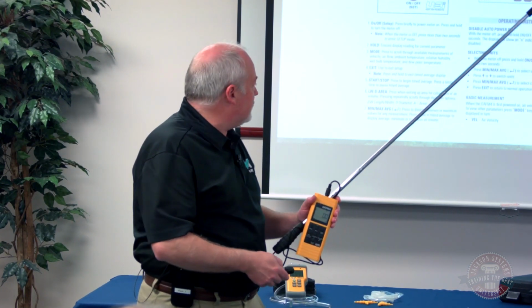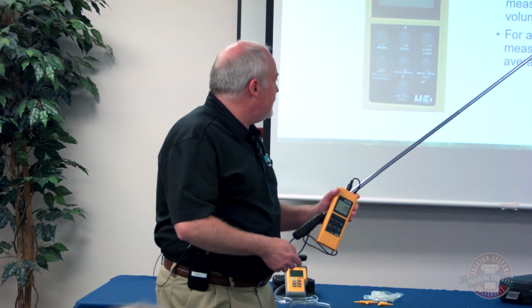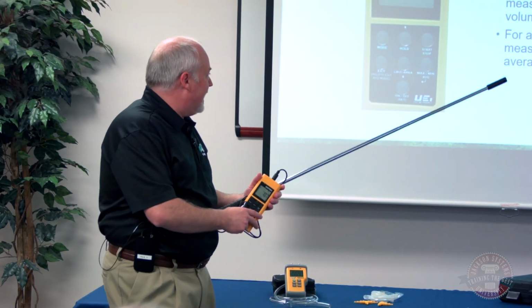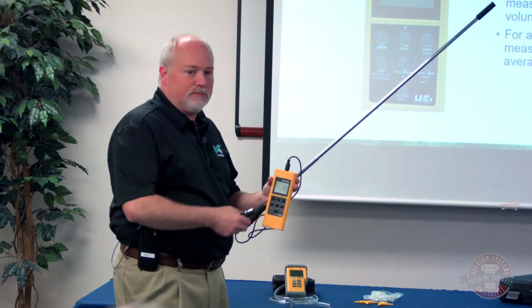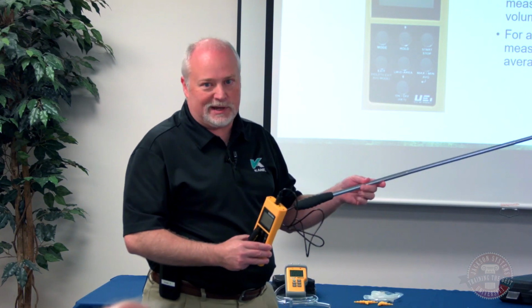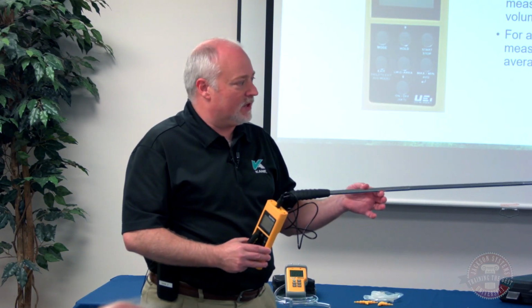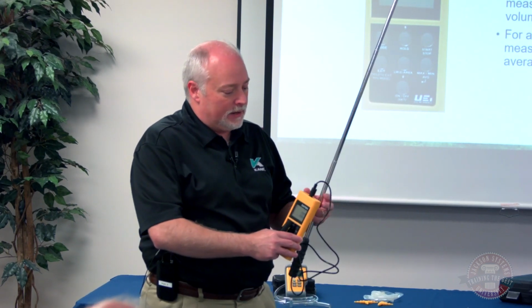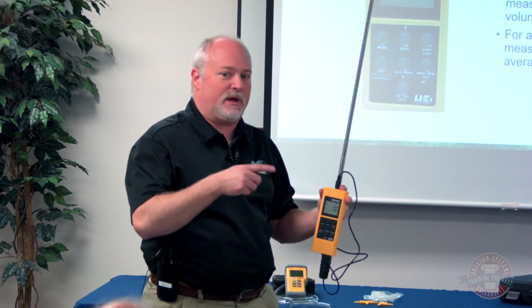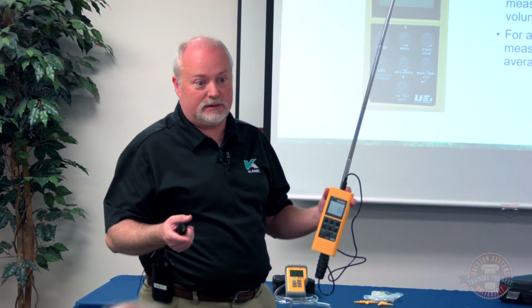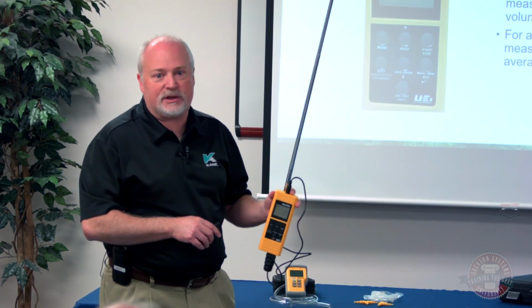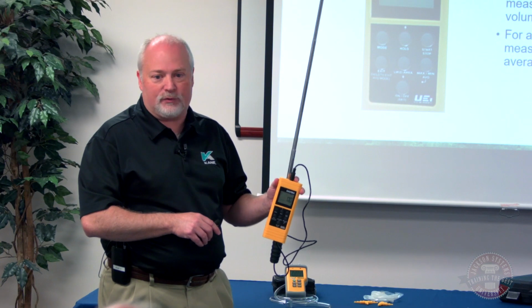But to measure air duct volume, if we just want to do a quick volume sample and simply estimate it, we can put this in volume mode, put it in front of a register or in a duct, and get a real quick reading that's going to give an estimate. But as we all know, the size of a duct, it's not going to flow the exact same amount of air all the way across that duct. You've got a little bit different air movement out by the edges versus in the center. So the best way to get the most accurate reading is a time average measurement.